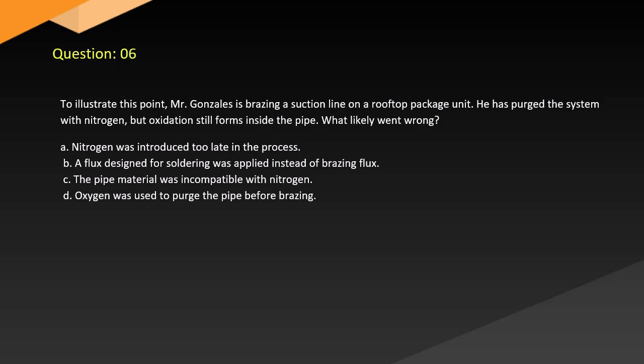Question 6. To illustrate this point, Mr. Gonzalez is brazing a suction line on a rooftop package unit. He has purged the system with nitrogen, but oxidation still forms inside the pipe. What likely went wrong? A. Nitrogen was introduced too late in the process. B. A flux designed for soldering was applied instead of brazing flux. C. The pipe material was incompatible with nitrogen. D. Oxygen was used to purge the pipe before brazing.